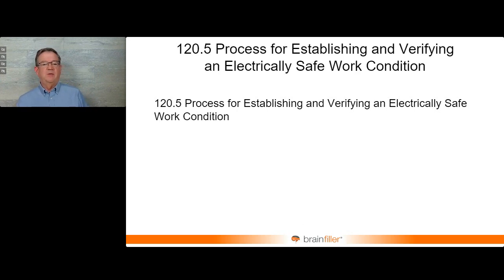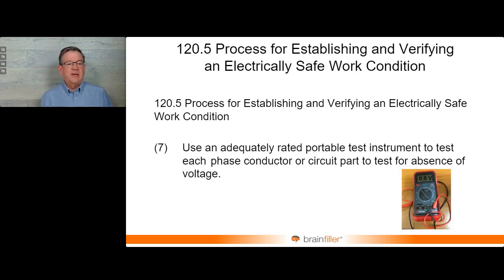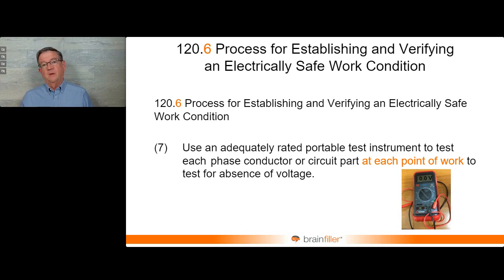The process for establishing and verifying an electrically safe work condition had a bit of a change to it. Step 7 in this: use an adequately rated portable test instrument to test each phase for the absence of voltage. That's where it's at. Until you've proven dead, you assume that it's energized. But there was some additional language added here. You test at each point of work. That wasn't in there before. It's like, wasn't that obvious? Well, again, if it's not in writing, how do you enforce it?